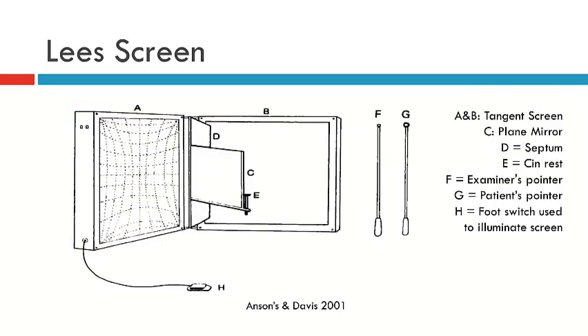Now what we didn't see in the photograph is that the Lees Screen also comes with a pair of pointers. One pointer is for the examiner and the other pointer is for the patient. We also have a foot switch or a foot pedal and this allows the orthoptist to turn on and off the screens so they can choose to illuminate which screen they choose at any point in time.